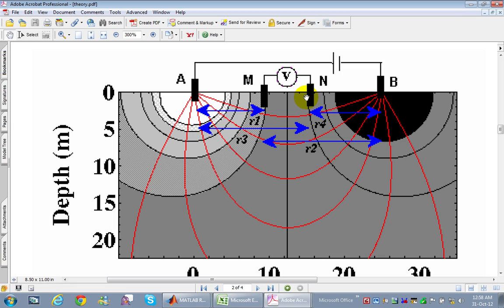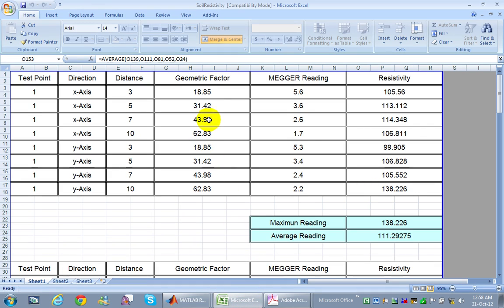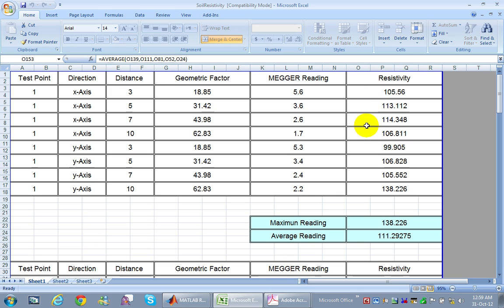After taking many measurements at different distances, we can determine the best layer for laying down the grounding grid. For example, if the resistivity at 3 meters is 105 ohm-meter and at 10 meters is 106 ohm-meter, the soil is approximately homogeneous since increasing the distance gives similar readings.